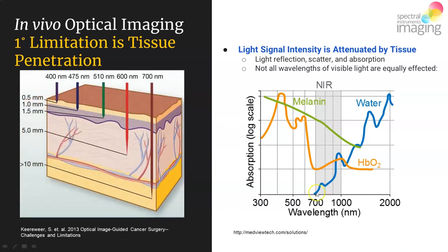What does this mean for the optical imager? The wavelength of light you use will strongly affect the sensitivity of your ability to detect your probe. If you select a probe that requires blue light, you will not detect any probe more than about half a millimeter from the surface. If you use a probe requiring green excitation light, you can have the probe slightly deeper — but still not much, basically one and a half millimeters. Using a probe excited by red light, you can go down to five millimeters.